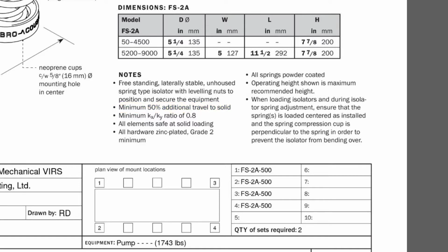We'll want to make sure there are no fully compressed springs on the job site by making sure there is still space between the spring coils. This note here is repeated from the installation instructions page because it's quite important to make sure the load is centered and that the compression cup stays horizontal to keep the spring from being bent sideways. Finally, in this area, we see the isolator selections and locations, which matches what we saw on the inertia base drawing.